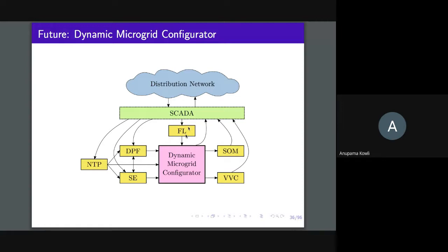This fault location, isolation, and restoration, FLISR, is the typical module existing in a distribution management system. Instead of FLISR, we could only have the fault location module, and replace the isolation and service restoration module with this dynamic microgrid configurator, which would decide which switches to turn on or off to isolate your microgrids and also do volt-var control. Does that make sense to everybody?